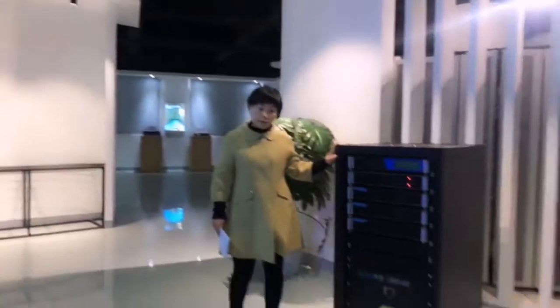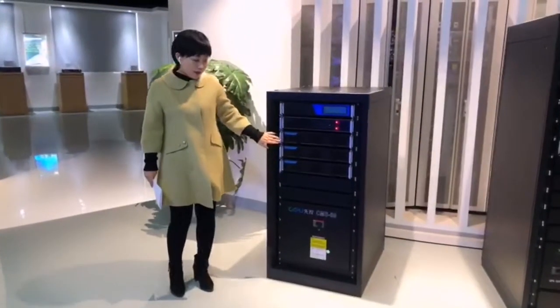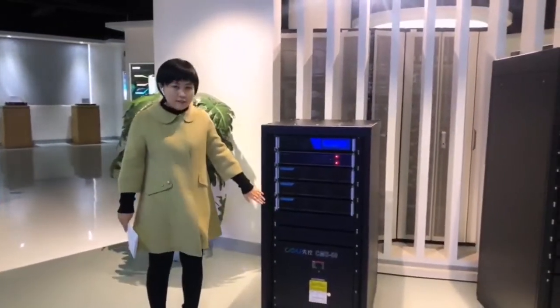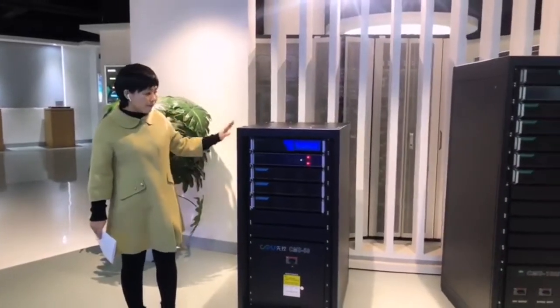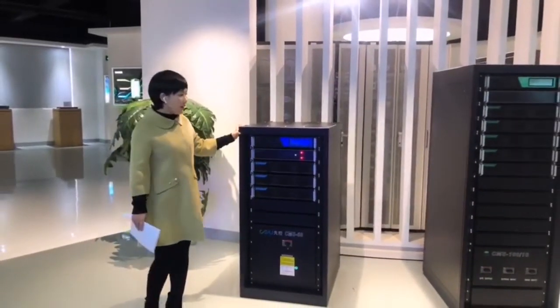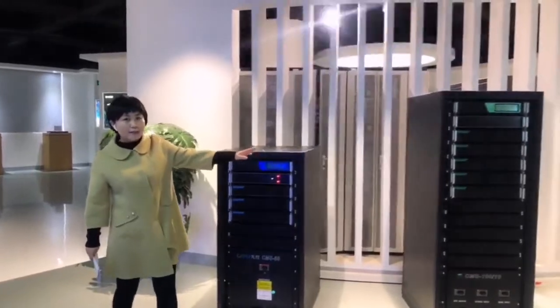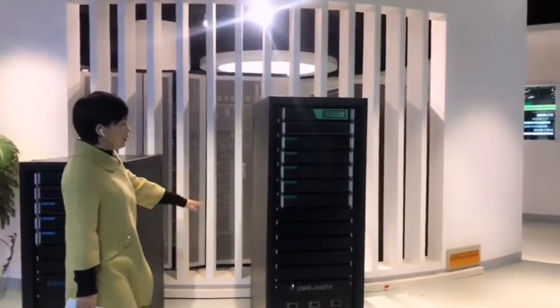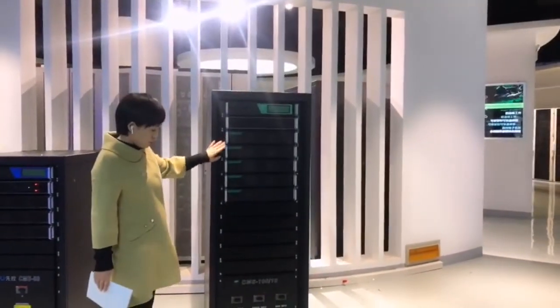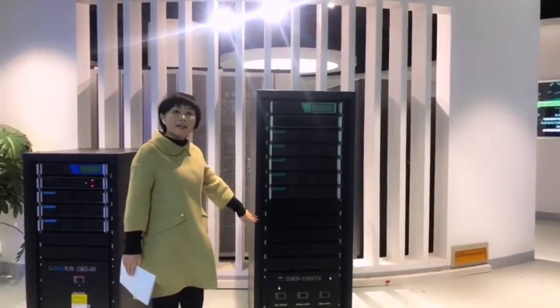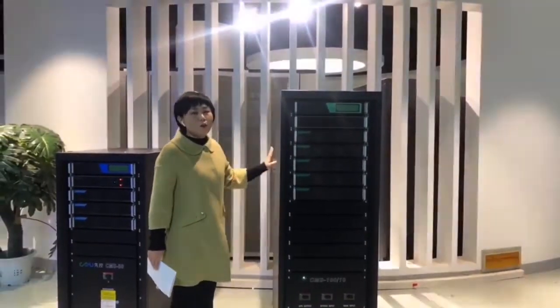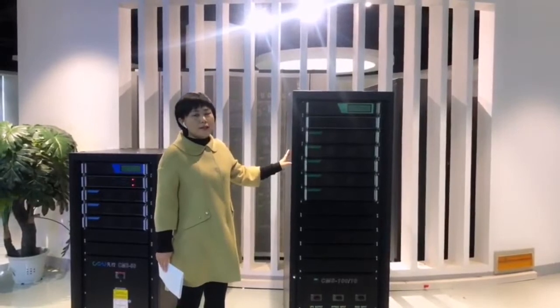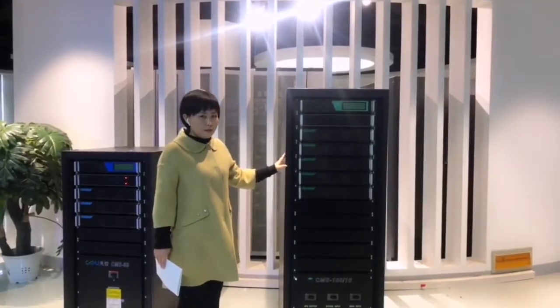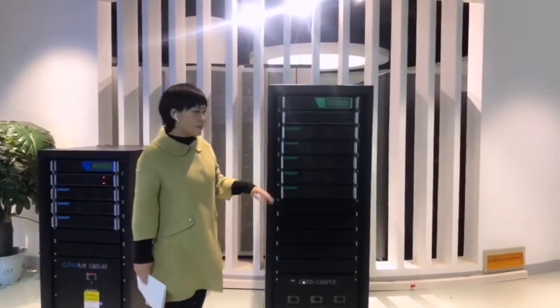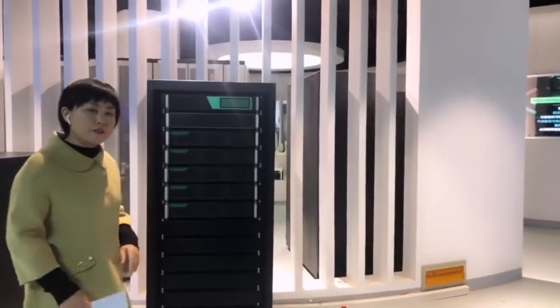Here we have the 10 kVA module and the 50 kVA rack. Okay, next one. The 10 kVA module and the 100 kVA rack. It's the older design. The battery is 64 blocks. The third generation of our modular UPS.